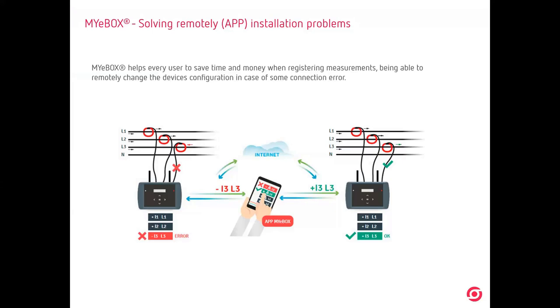And the same when the voltage and current are not matching, okay? Voltage and current should be measured on the same line. If you are not measuring current and voltage from the same line, you will not have correct measuring in power factor, in power, in energy, in cost fee. So you have to come back again and change the cabling, etc. Now with the APP, you are able to match voltages and currents remotely. Okay, and also the scale of the clamp. If you have made a mistake with the scale of the clamp, remotely you can change it.